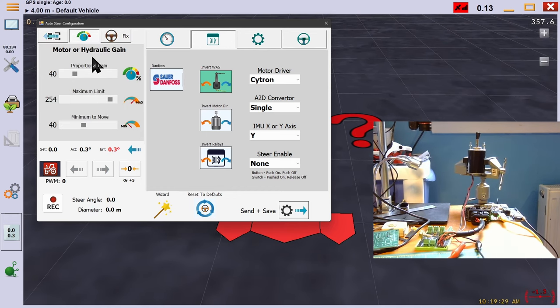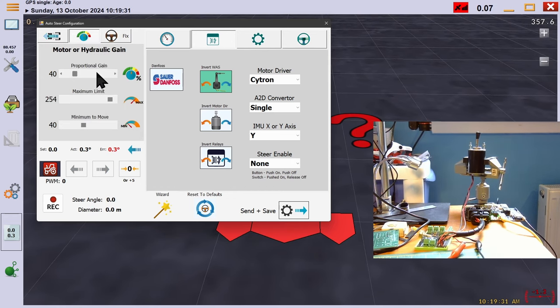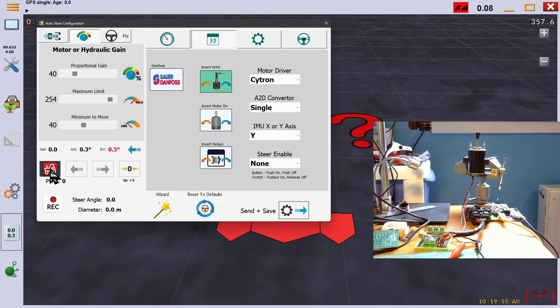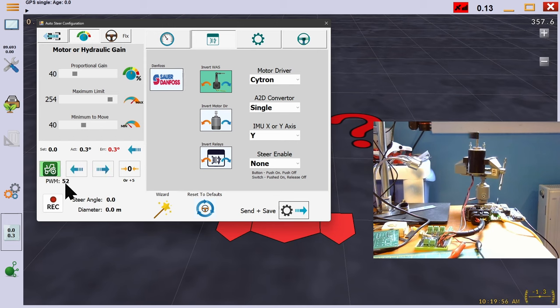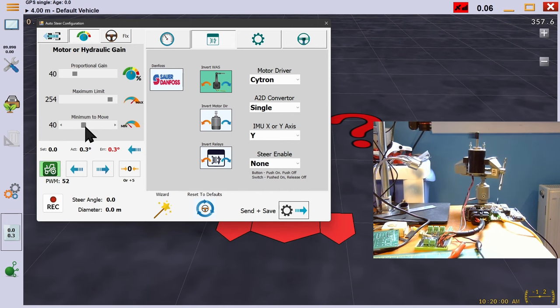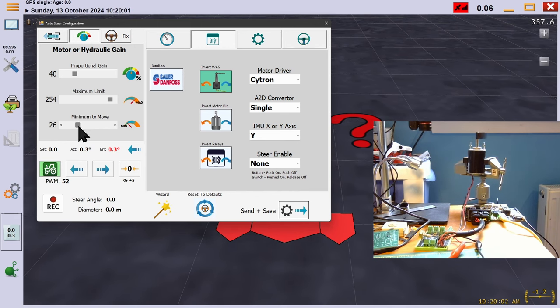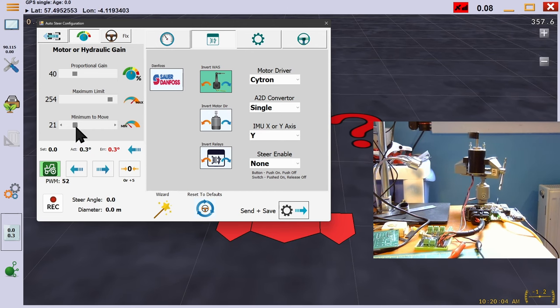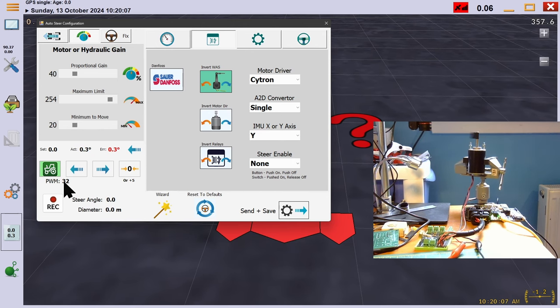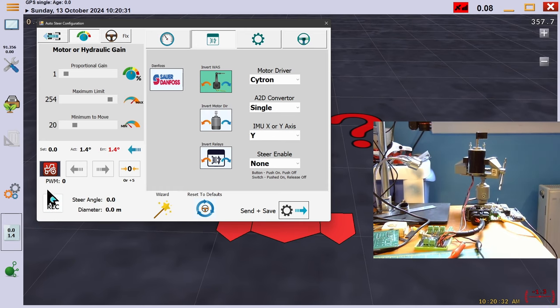Let's look at our PWM settings. If you've watched the understanding PWM video, you will know how the output PWM is calculated, but to remind, the error is multiplied by the proportional gain, and then the minimum is added. In this example, 0.3 times 40 is 12, and add the minimum of 40, and you get an output of 52. If we bring minimum PWM down to 20, then it's 12 plus 20 which is 32. We'll move the wheel angle sensor over a little so it's above 1 degree and lower proportional gain to 1.